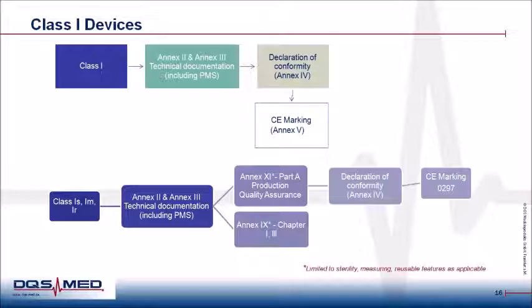But if a class 1 device is supplied in sterile form or has a measuring function or is a reusable surgical instrument, then a notified body involvement is necessary. A limited quality management system must be in place to control the production or to control the special characteristics. As mentioned, a notified body involvement is required to control how the QMS manages those specific features in regard to the conformity assessment procedure selected by the manufacturer.